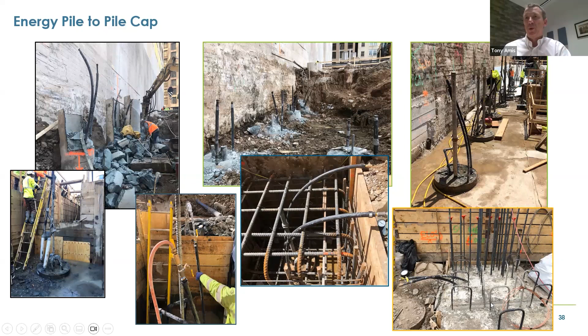The important part here is that once the pile is tested, a key hold point for proceeding with construction is to check whether the pressure gauge shows the system has held pressure, before they concrete the next stage. Once the pile caps are formed, it's a case of running geothermal loops back through to the sub-manifolds.